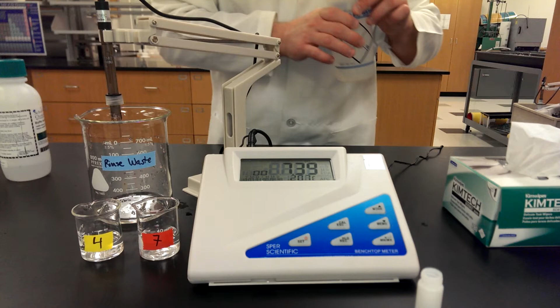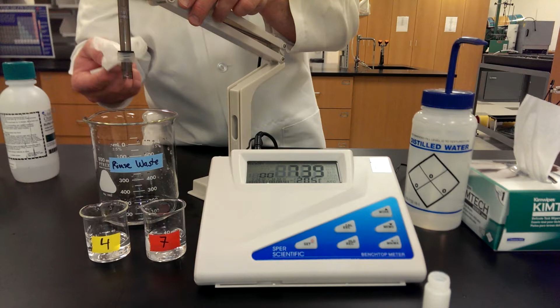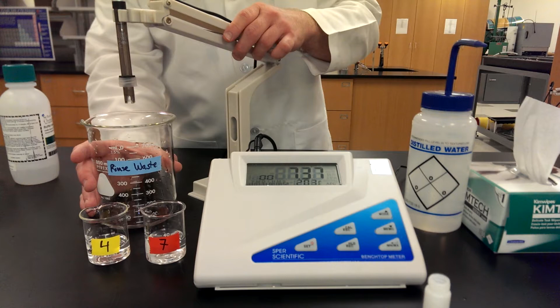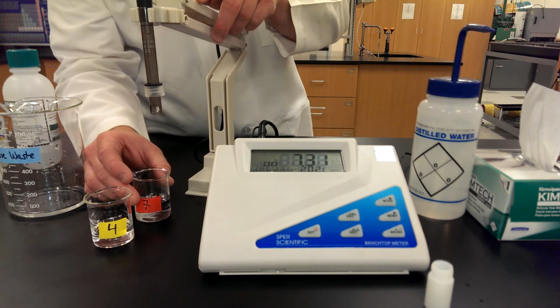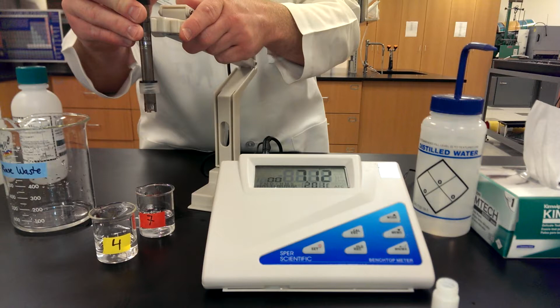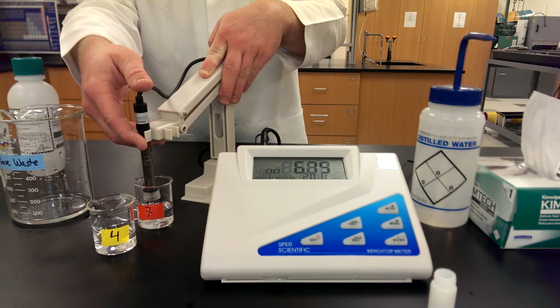We're going to take a Kimwipe and gently dab around the outside of the probe. Never jam this on the inside of it, just dab around the outside. Dry up some of that extra DI water. And after we do that, we're going to take our pH 7 buffer, which I've already poured in this 50 ml beaker, and we're going to put our probe into the beaker. You can do this by holding it in there with your hand or pushing it down inside like this.